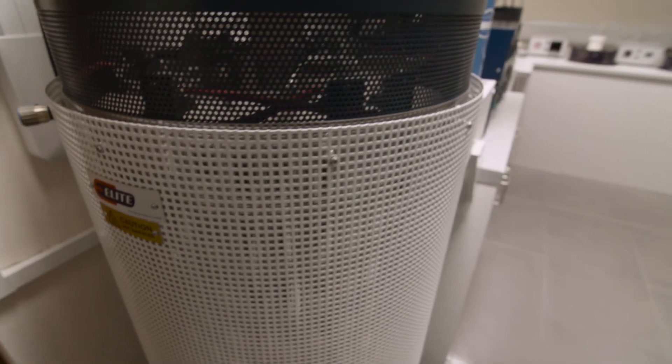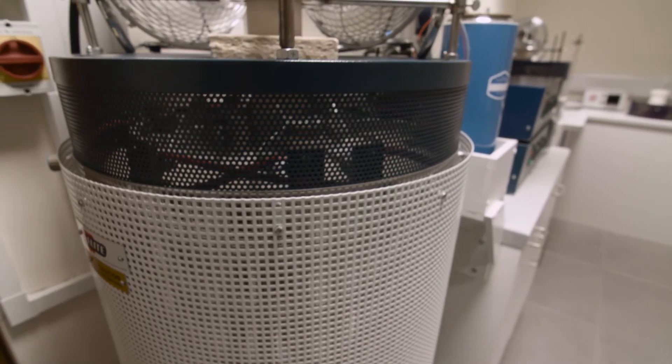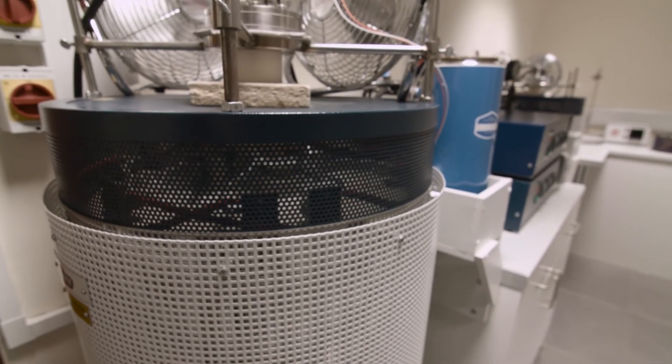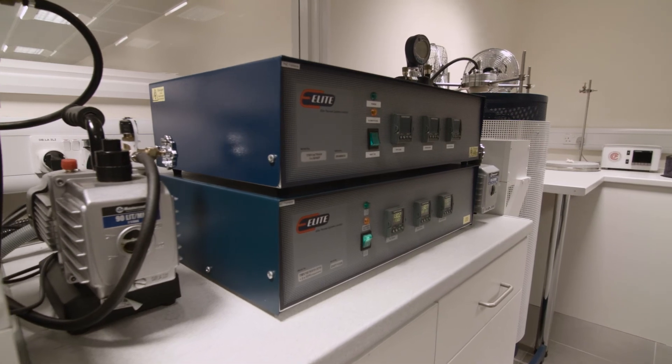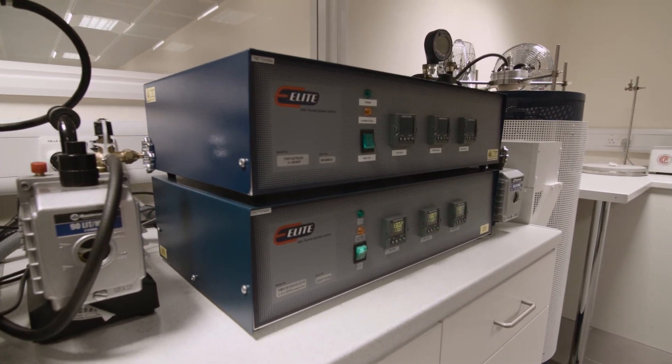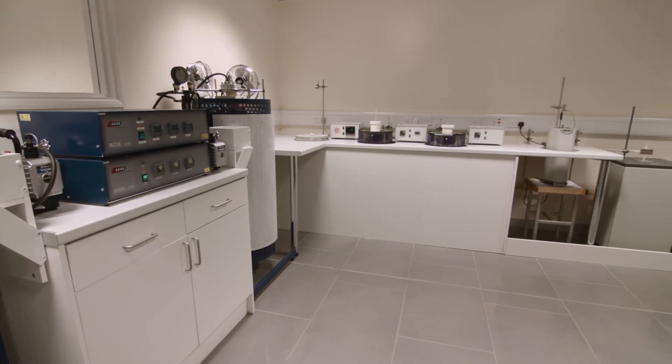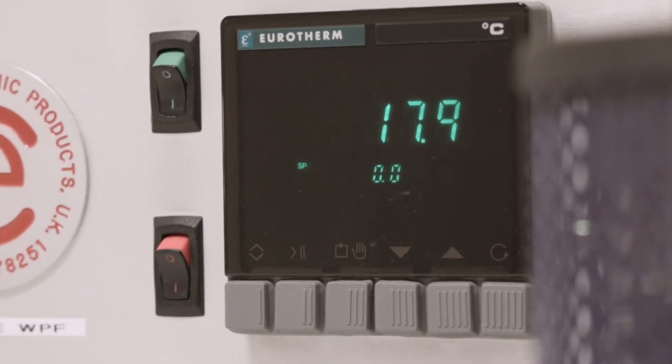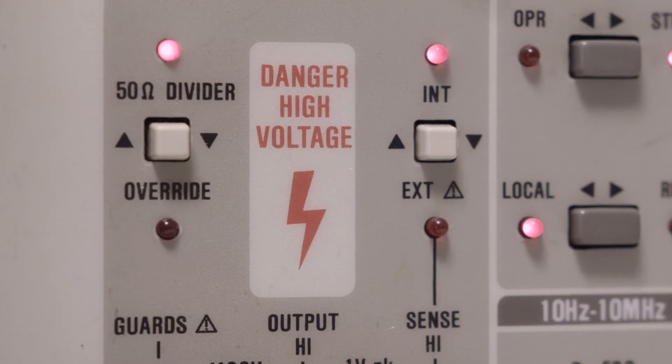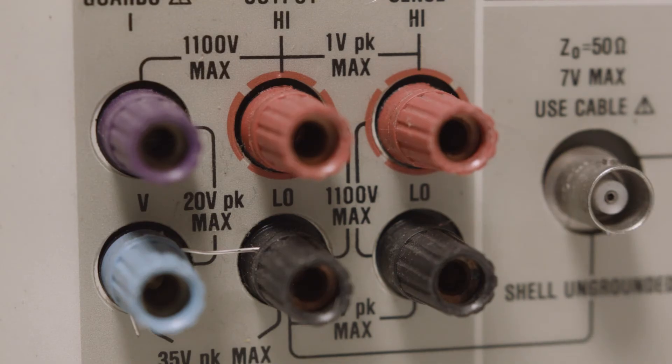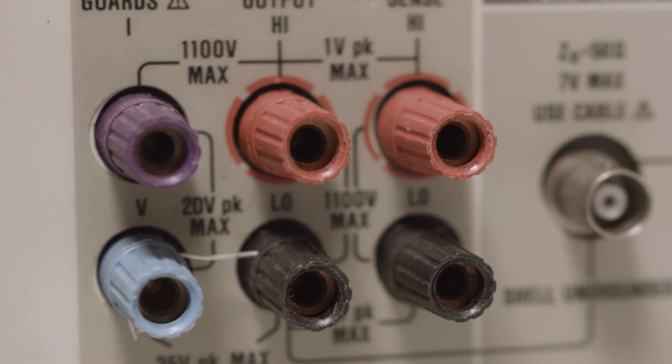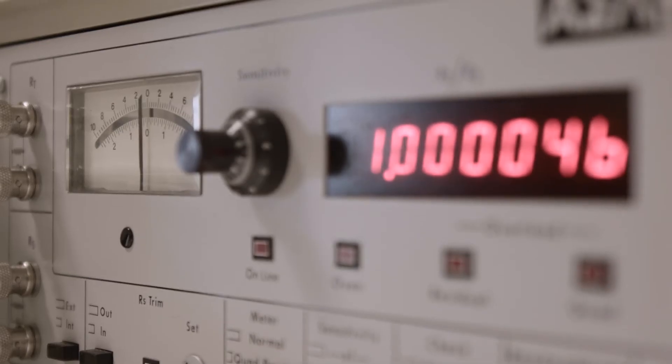The lab has a range of fixed point furnaces. In each of the furnaces, there is a graphite crucible containing a pure metal which is a minimum of 6 nines purity. In the lab, we use reference thermocouples calibrated using these fixed point systems. We apply these directly in all of our thermocouple comparison calibrations and this is how we make every measurement at every level with the highest degree of accuracy.